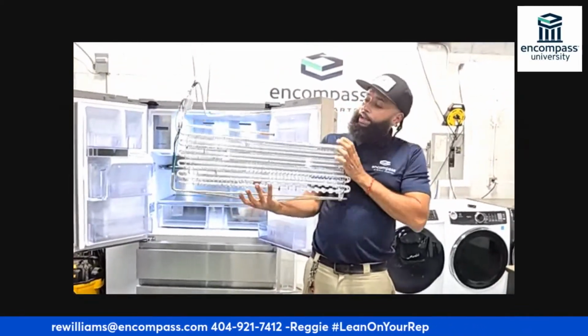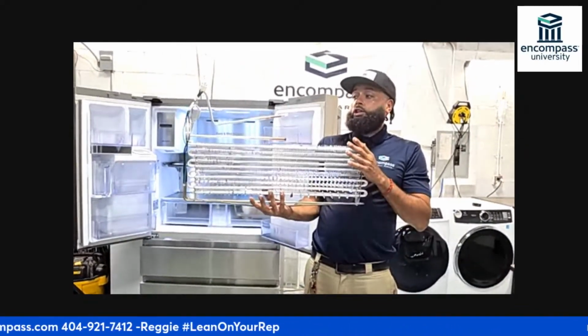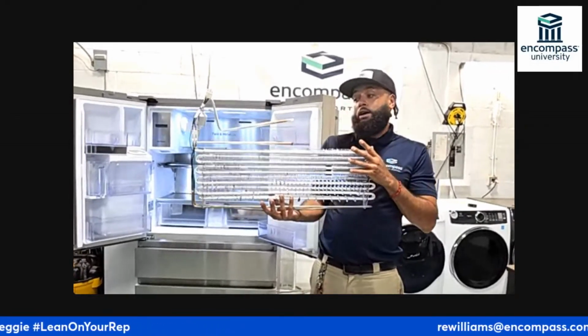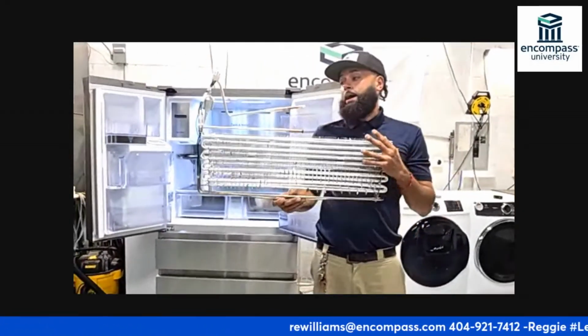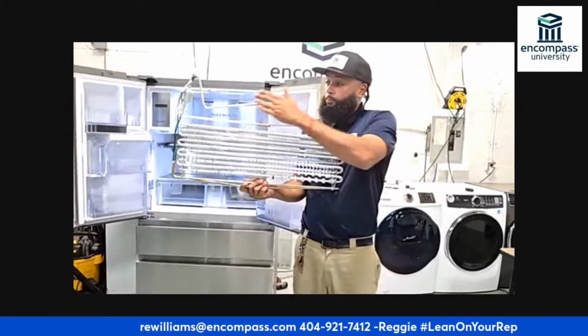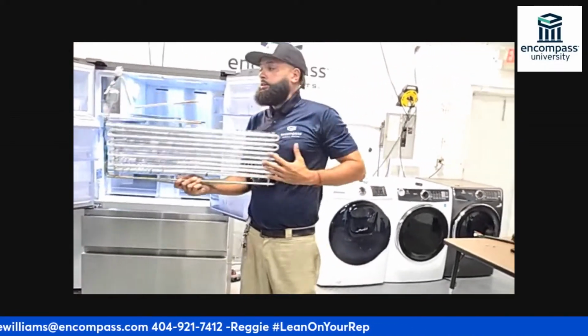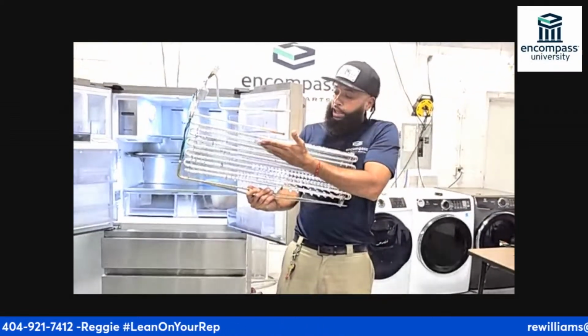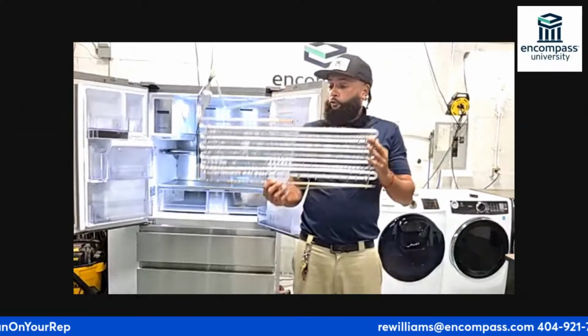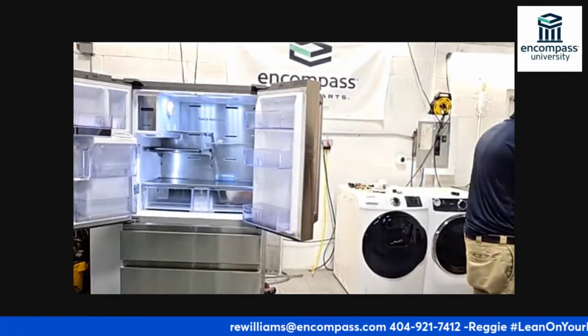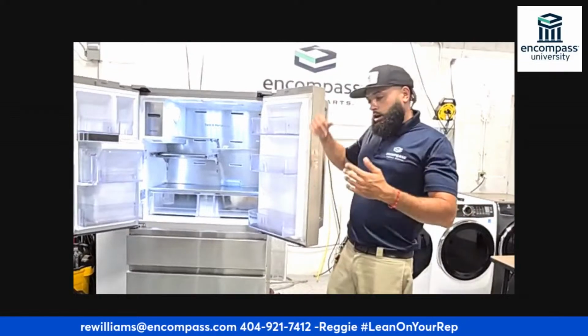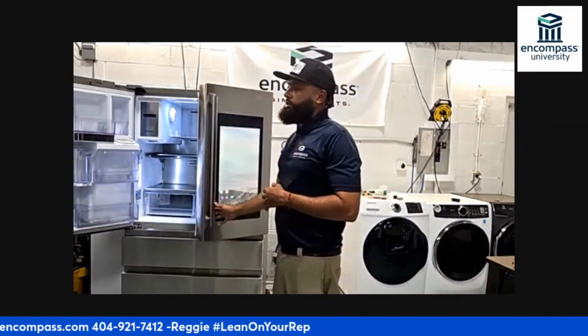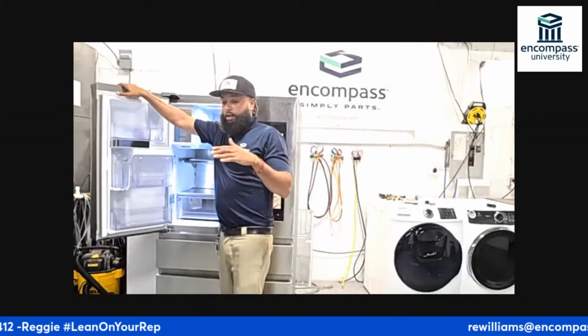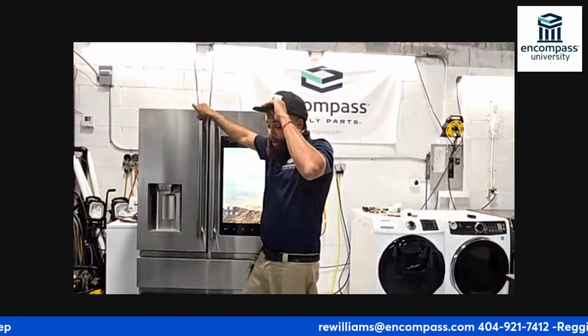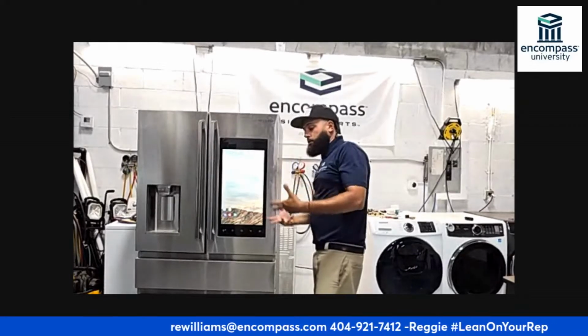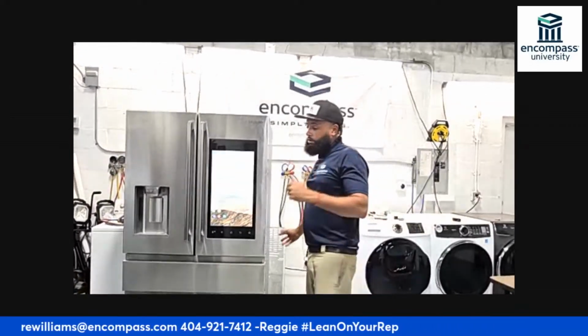This is right now a dry evaporator coil. If your fridge has a dry evaporator coil, that's bad. You want to make sure your evaporator coils have frost on them, and more importantly, a full frost pattern, not partial. If the fans, compressor, and all components are working, and we've checked the coil patterns, the next thing is to get our manifold gauges and look at the compressor.